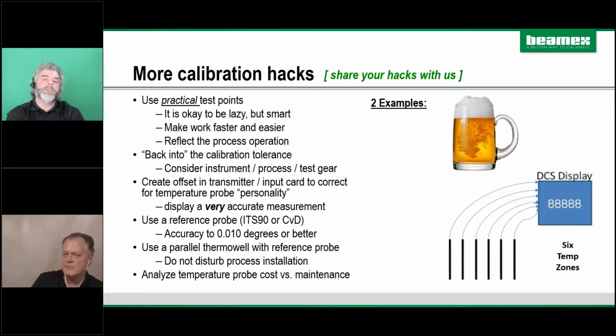Part of the point is you don't have to throw these probes out and get more accurate ones. If you know what they're reading, you can put that offset in and have reliable numbers. This kind of application would definitely want 4-wire RTDs. Spend the extra money so you're really tuned in on what you're trying to do.